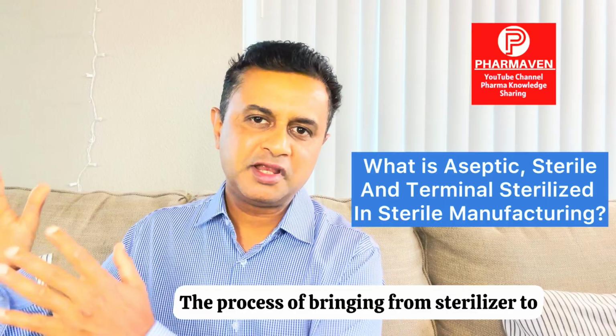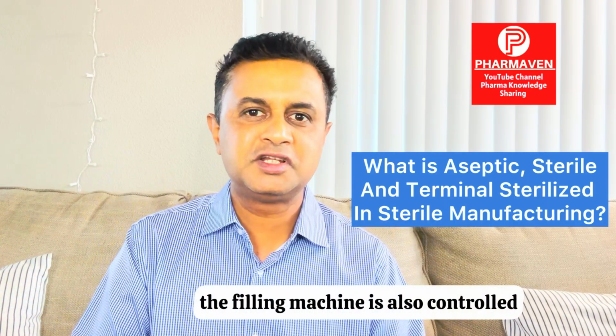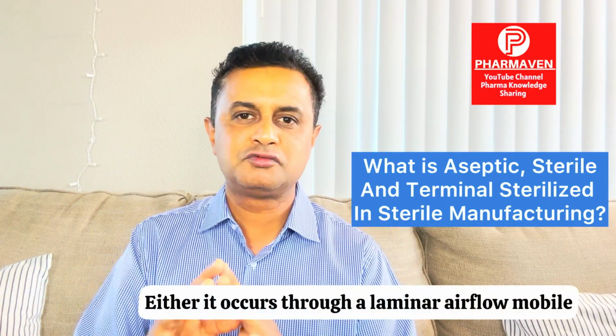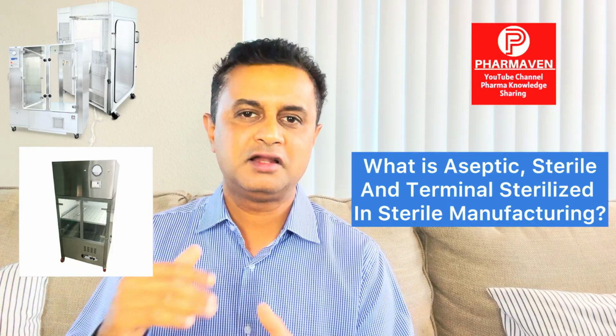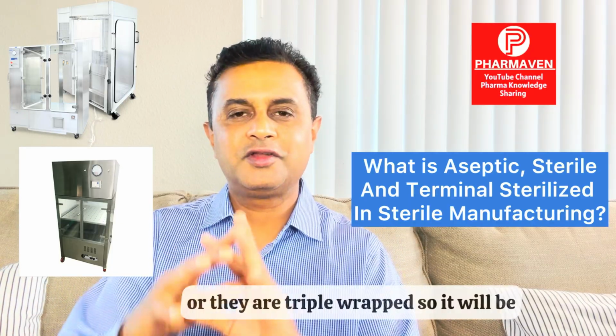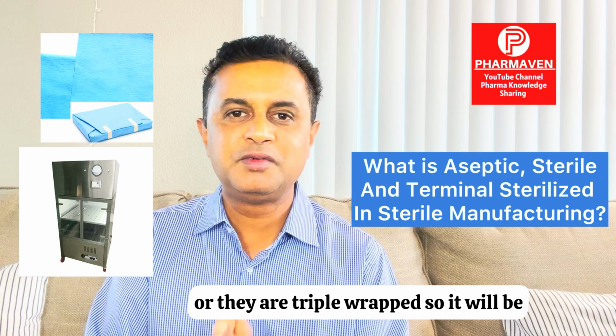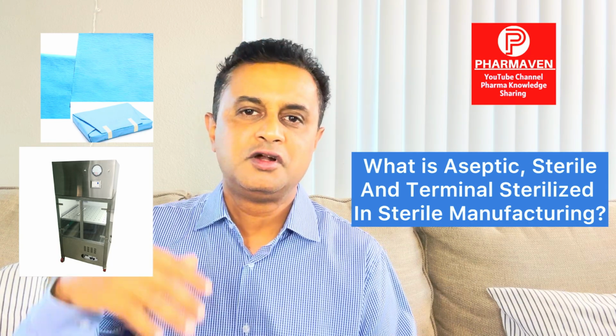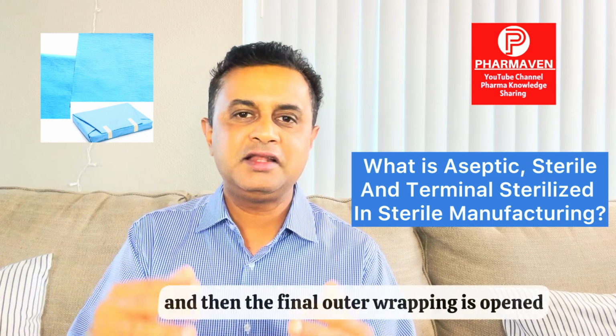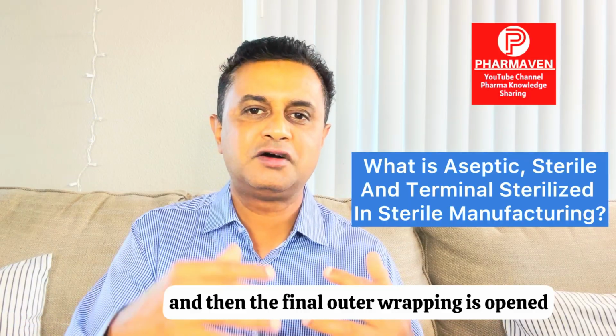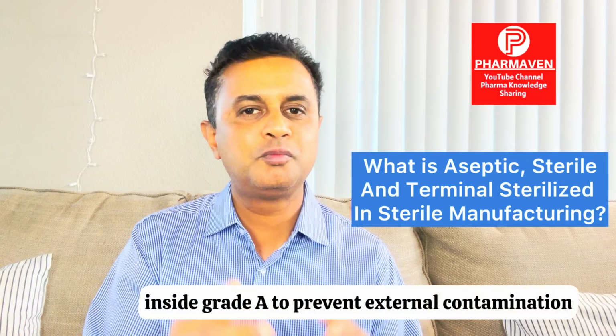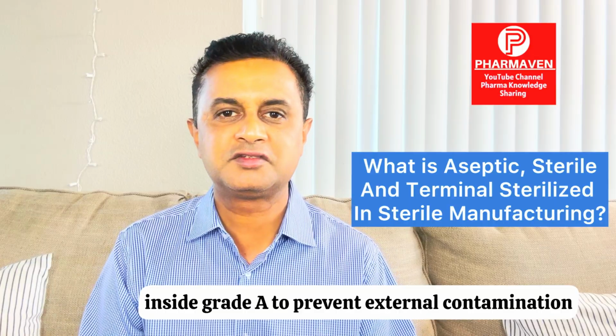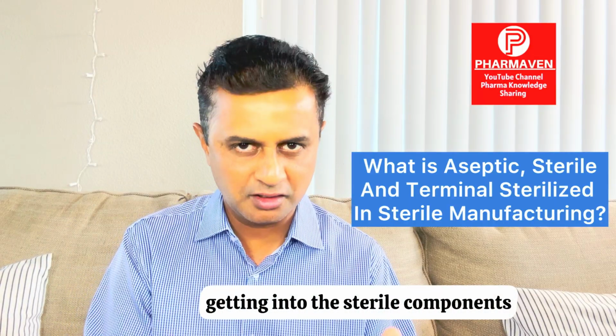The process of bringing components from the sterilizer to the filling machine is also controlled. Either it occurs through a mobile laminar airflow cart, or they are triple wrapped, so they are protected from exposure to the outside environment. The final outer wrapping is opened inside grade A to prevent external contamination getting into the sterile components.